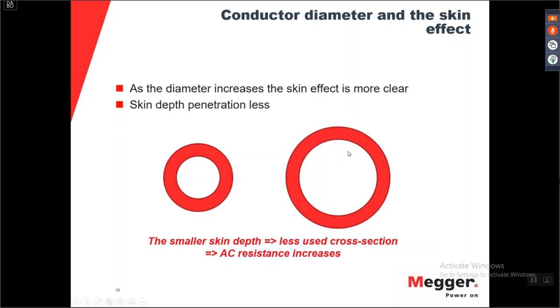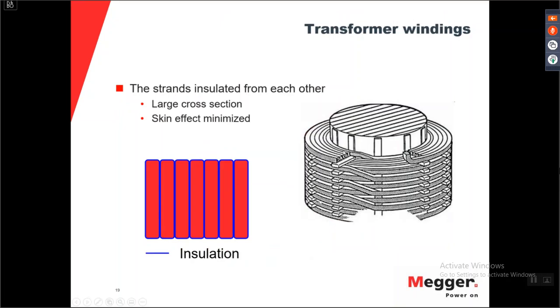So how do they do it when they make the transformer winding? They actually separate these different conductors. So they make smaller effect because you will only have a small part between all these parallel strands. So here is one parallel strand, and here is how it's done in the transformer winding. So you have all these parallel strands in one turn.